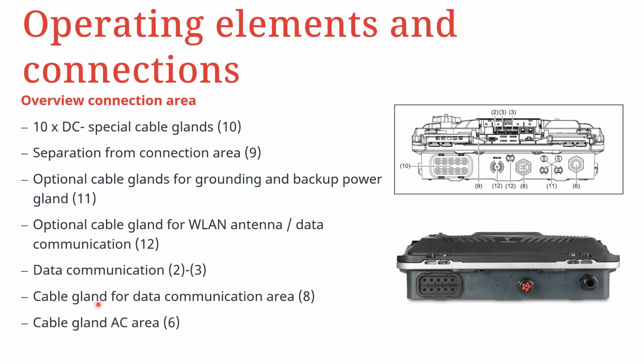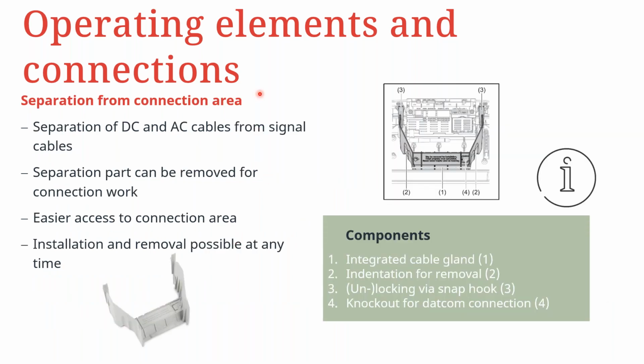And then you have the cable gland for data communication, which is position number 8 here, and the cable gland for the AC connection, which is number 6 here, which comes provided, as you can see. So this is the one for data communication, and the one to the right here is for the AC connection. As far as the separation area is concerned, this allows the separation of the DC and AC cables, as I had mentioned before. So they are kept separate from the data communication area.